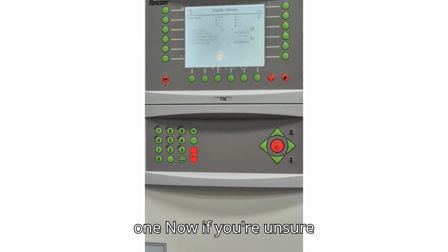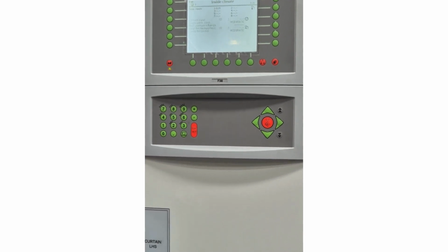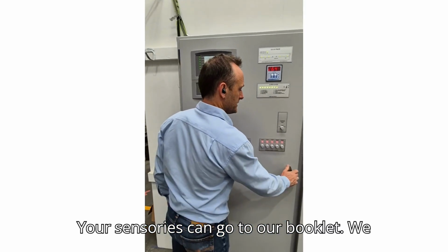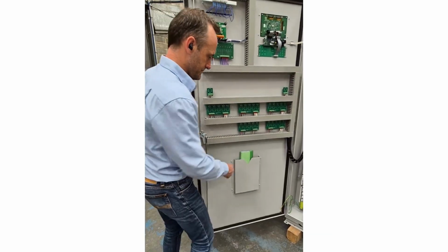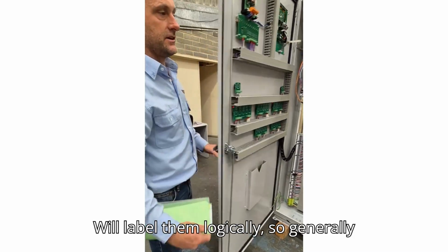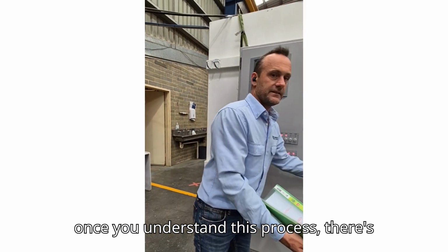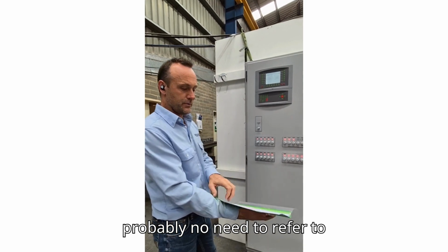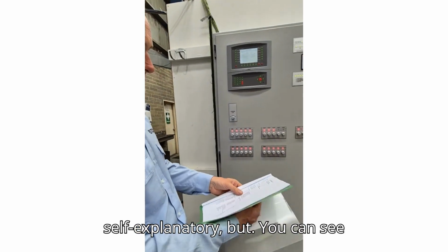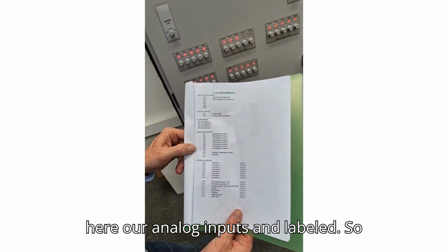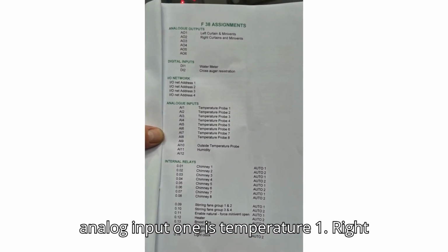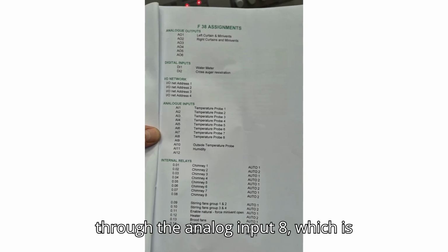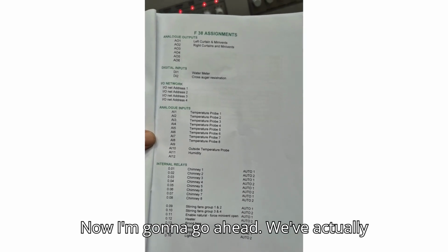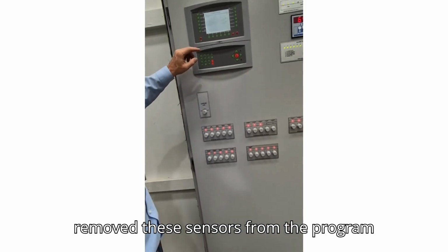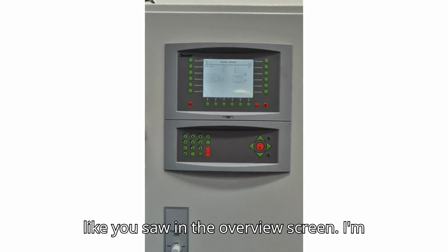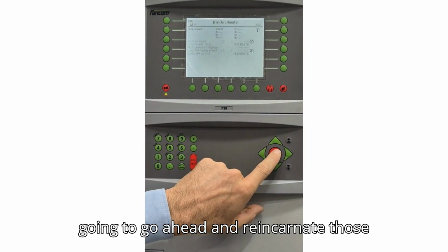Now, if you're unsure what analog input your sensor is, you can go to our booklet within the cabinet and find out. We label them logically, so generally once you understand this process, there's probably no need to refer to the booklet. It's pretty self-explanatory, but you can see here our analog inputs are labelled. So analog input 1 is temperature 1, right through to analog input 8, which is temperature probe 8. It's pretty logical. Now I'm going to go ahead, we've actually removed these sensors from the program like you saw in the overview screen. I'm going to go ahead and re-include those sensors.